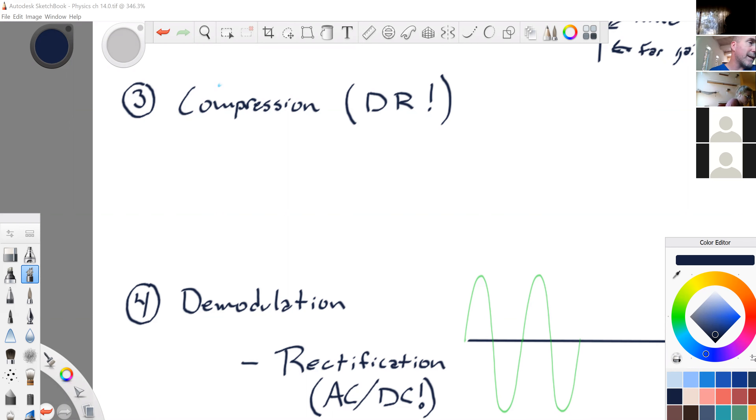Important to note: although increased dynamic range makes a nicer, more meaningful image, lower dynamic range increases contrast resolution. With lower dynamic range it goes from bright to anechoic really quick — so there's more contrast, therefore more contrast resolution. But that's a kind of resolution I'm not sure I want.